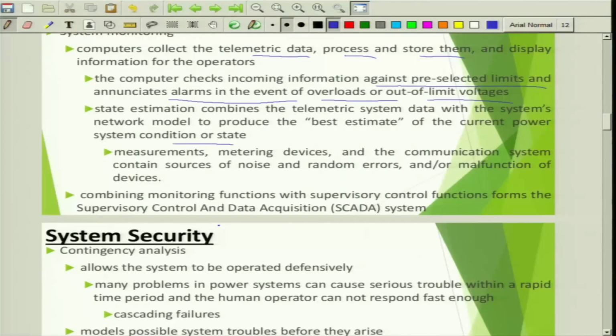Combining monitoring functions with supervisory control actions forms the supervisory control and data acquisition. This is called SCADA. You collect the data, and supervisory control action takes place. This is the SCADA system. Across the entire country, the SCADA operators will be there. They would ensure the system operates properly. So, regional load dispatch centers, state load dispatch centers, and finally the national load dispatch center, NLDC. Different levels of hierarchical control action take place, so that the entire national power system security is not violated.